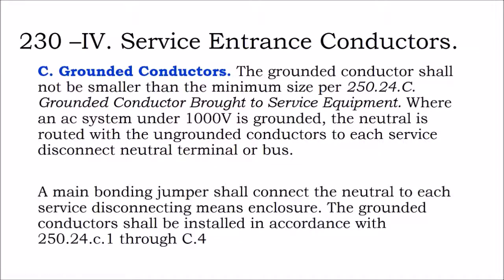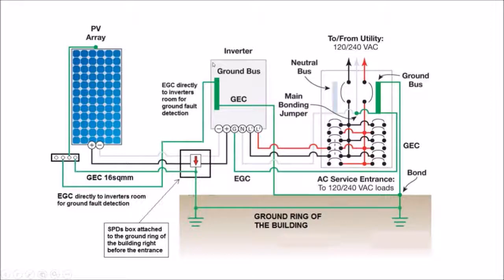the neutral conductor. The size of it is governed by a particular table in the National Electric Code. Where an AC system under 1,000 volts is grounded, the neutral is routed with the ungrounded conductors to each service disconnect. So your neutral is going to be running throughout the system. Now let's look at this wire diagram here. Now we have our, let me get my laser pointer out.